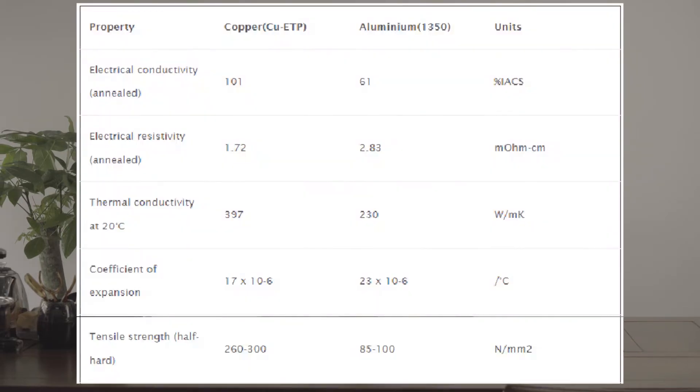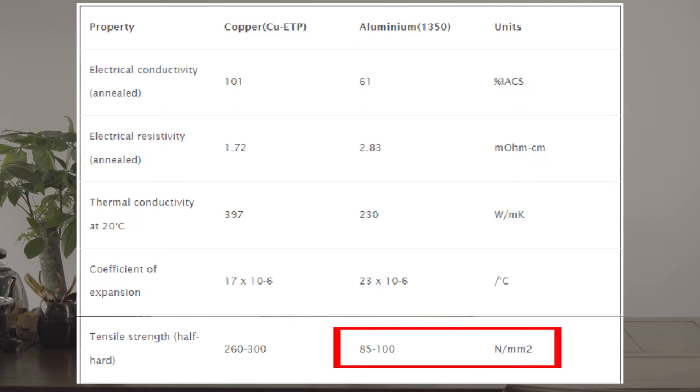The last point is their resistance. Some people argue that aluminum busbar cannot withstand electromechanical stress as well as copper busbar. But in reality, aluminum busbar has plenty of tensile strength to withstand thermal expansion stress. What's more, high quality, high strength aluminum busbar can have mechanical strength up to 530 Newton per square millimeter.